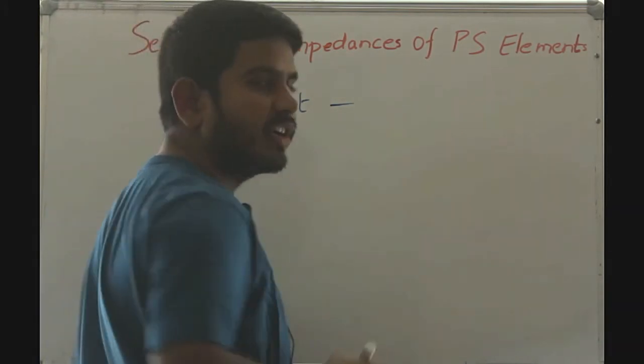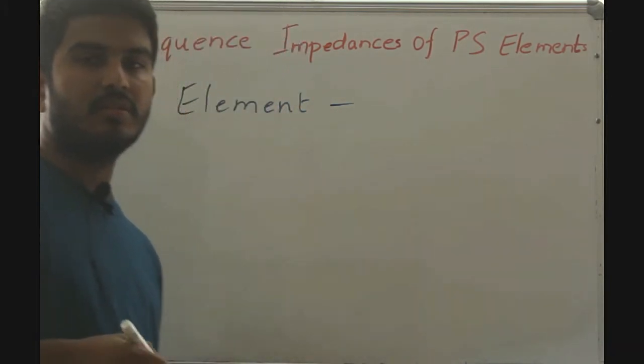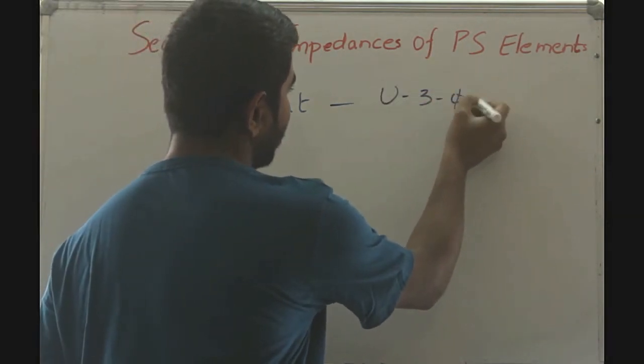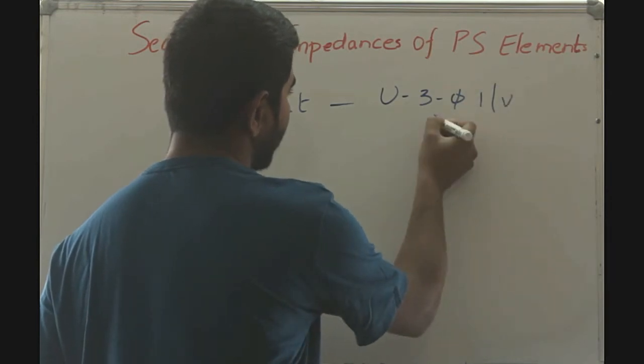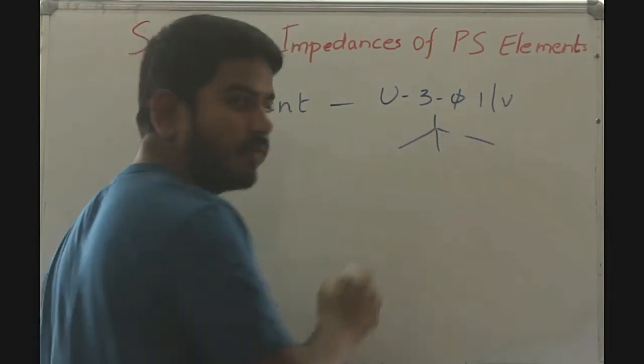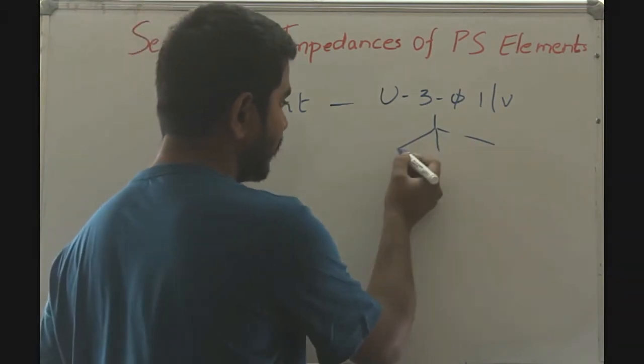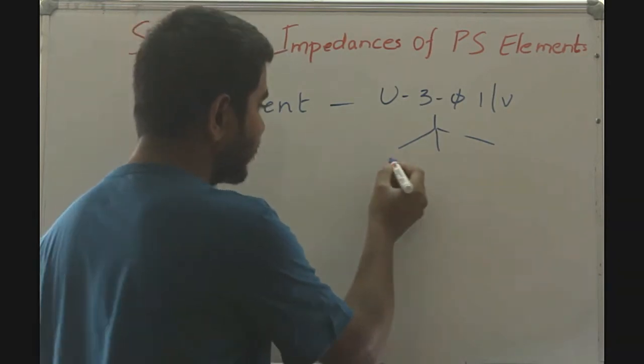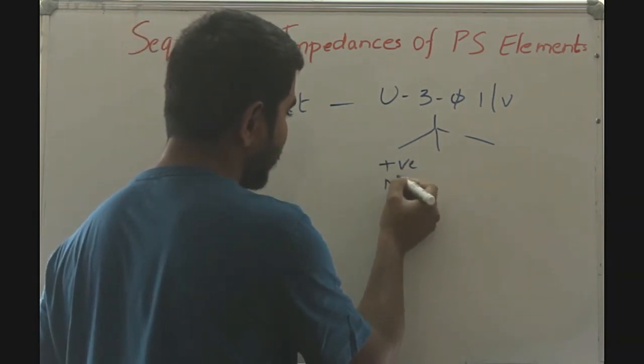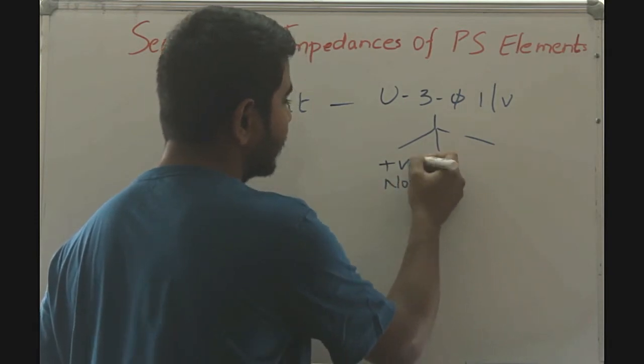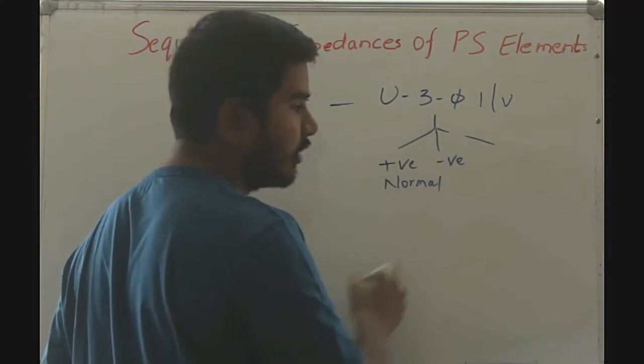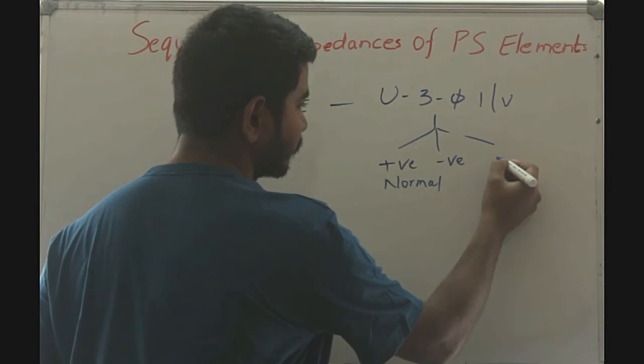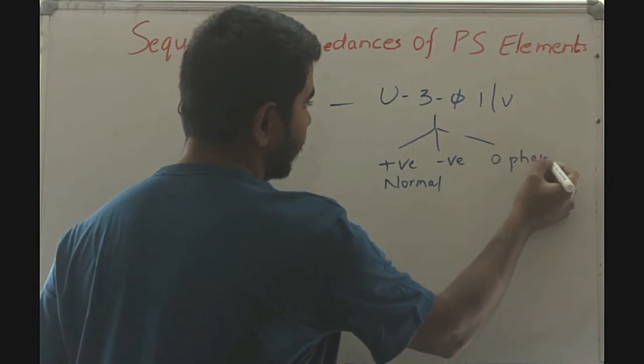In unsymmetrical fault conditions, according to Fortescue's theorem, an unbalanced three-phase current or voltage can be resolved into three separate sets of balanced vectors. One set consists of a balanced three-phase system with positive phase sequence, another set has a negative phase sequence component, and the third set is a co-phasal quantity with zero phase sequence component.